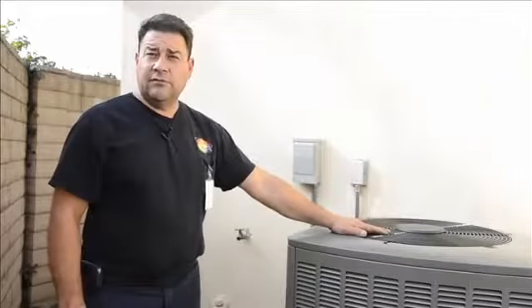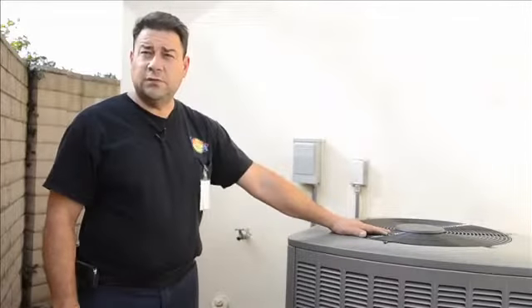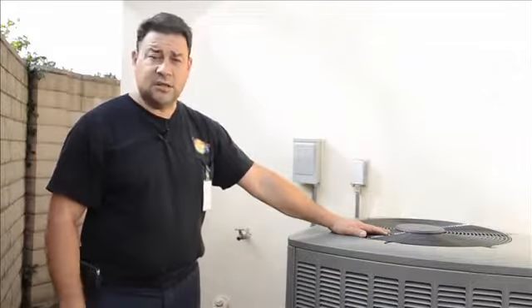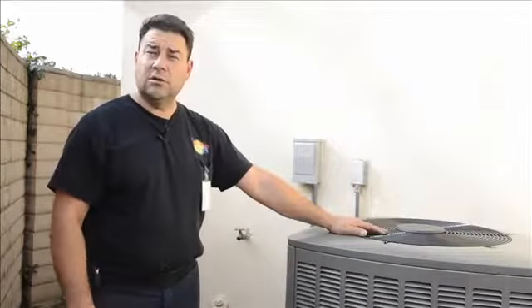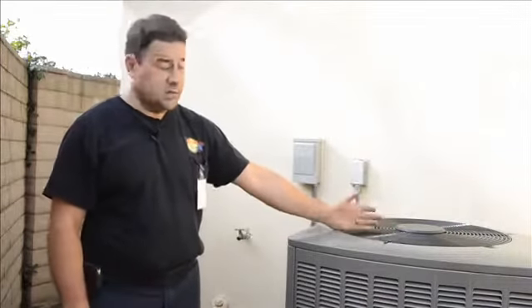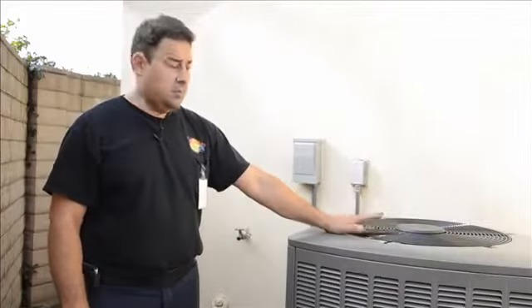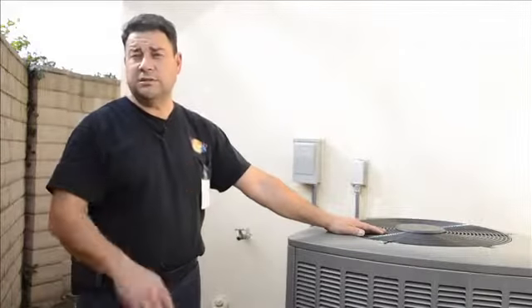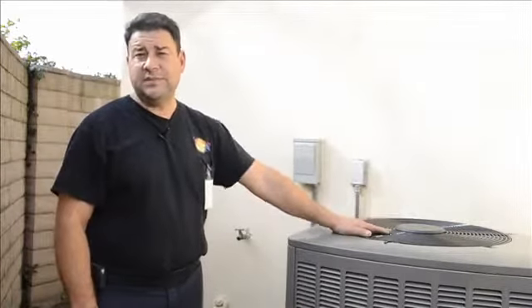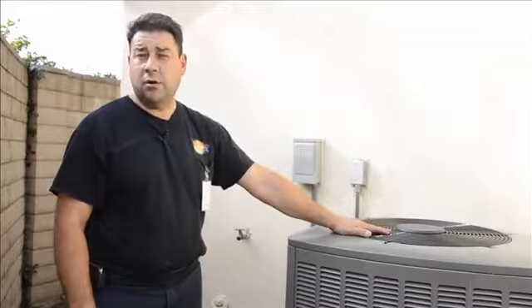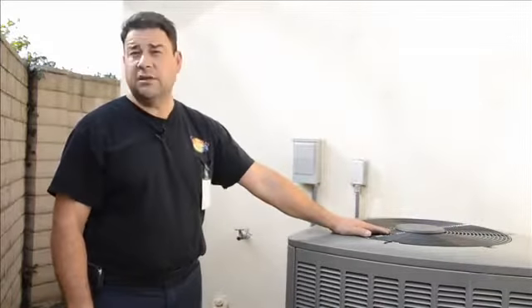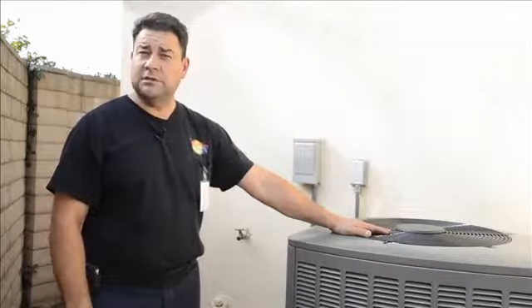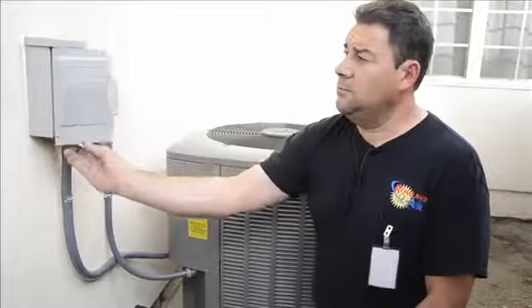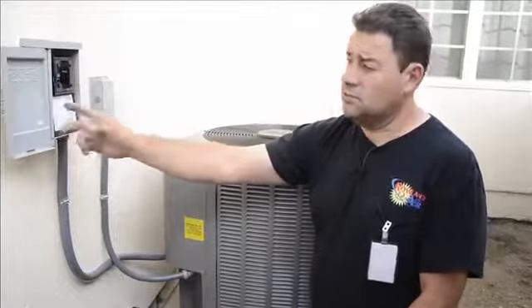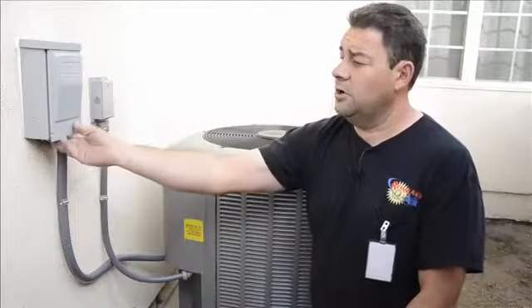Alright, today we're standing in front of the brand new Lennox XC14 installed in the homeowner's house now, the finished product. Earlier in the video you saw the old piece of equipment and heard it run. This one actually is running. This one, matched with the proper furnace and coil inside the attic, will achieve 15 SEER, 12.5 EER, which is a significant energy savings compared to the old piece of equipment. You're going to see the properly mounted fusible disconnect box. It's a weather-tight fusible box.